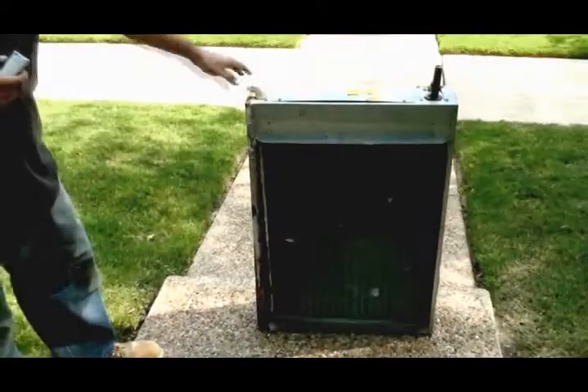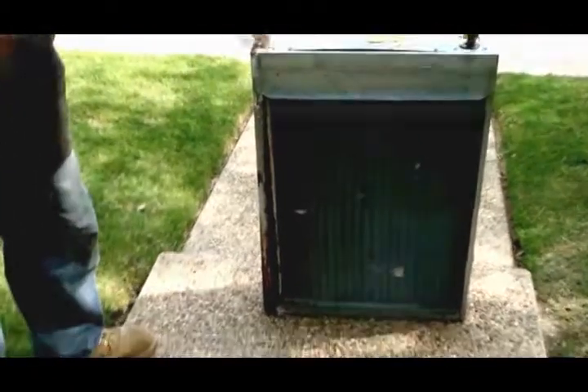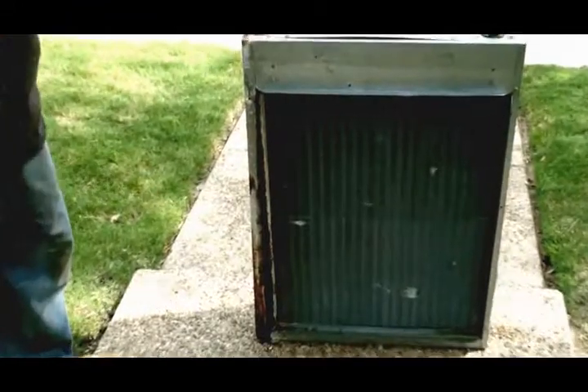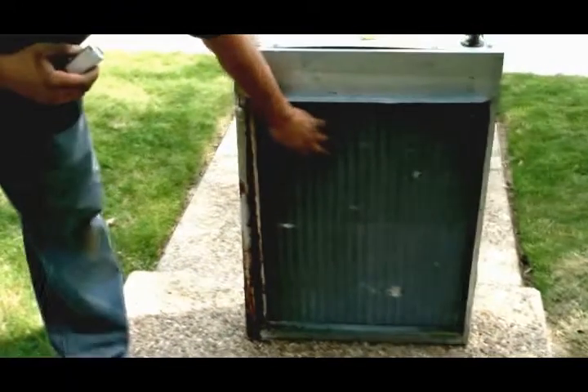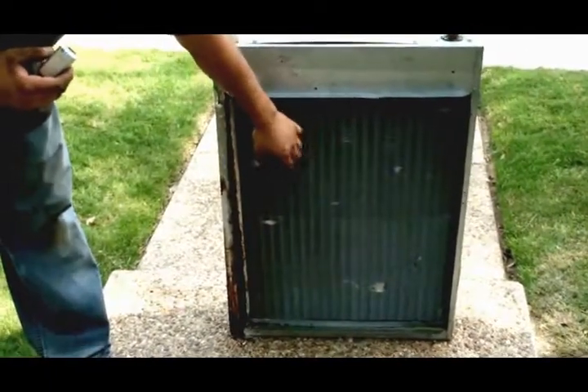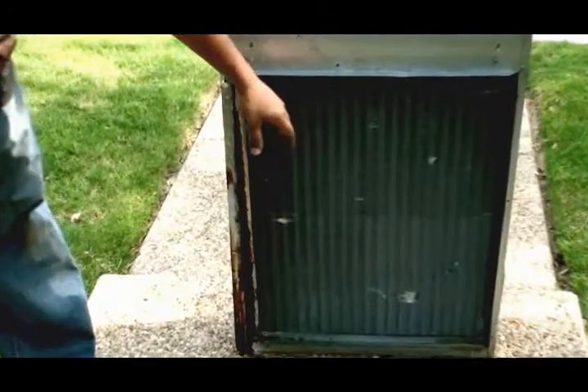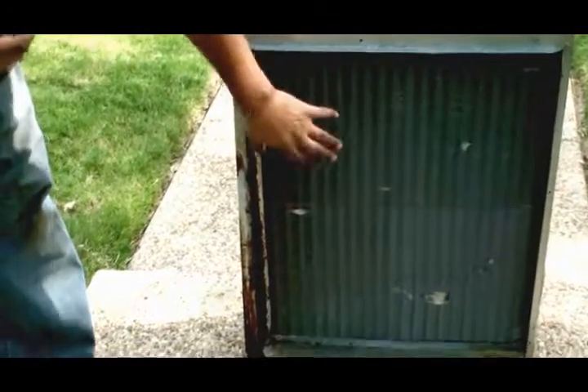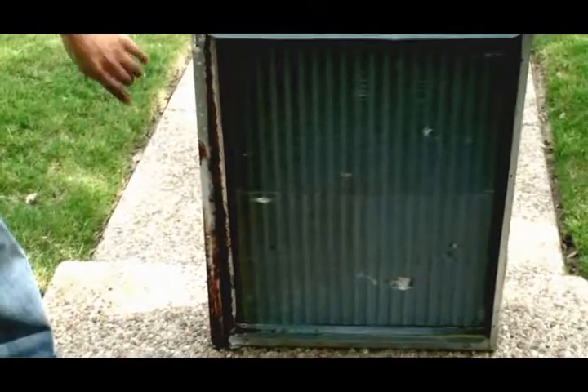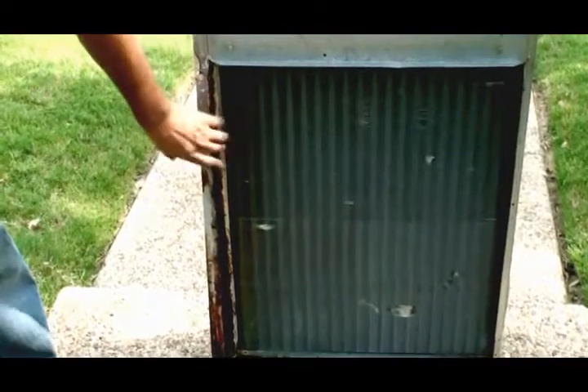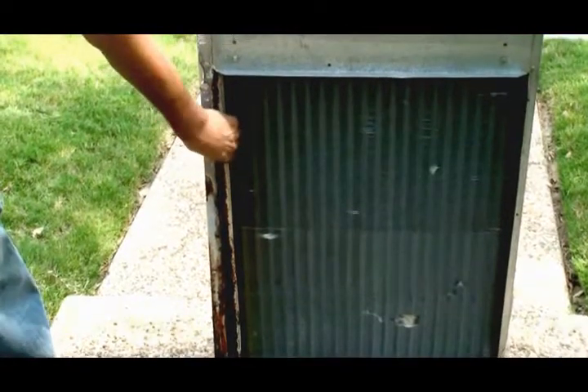All right, so basically this is just a prime example of a coil that is actually in decent shape. If you can see the fins right here, they're actually pretty decent, where the homeowner was actually changing their filter out, and it's not too caked up with dust or anything. But the big problem with this one was the drain pan. It's completely rotted out.